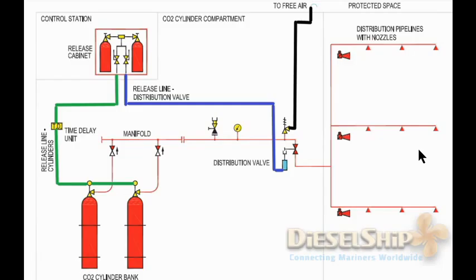There is a requirement that 85 percent of the CO2 has to be released within two minutes of operation. All pipings, nozzles, and diameters have been calculated so that this requirement is met. The details of the calculation — pipe diameter, length, and thickness — can be found in the CO2 manual.